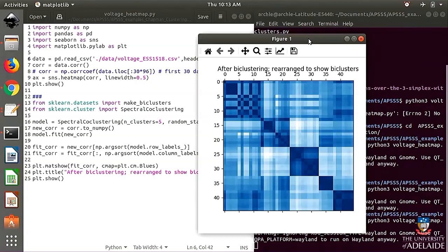Yeah, but not in this case. But it's good thinking. The big thing that we've done with this, we do a bit of phase identification. We've got customers on a phase, in a group of, say, 10 or 11 customers, and that one customer in particular is pulling a significant amount more load.